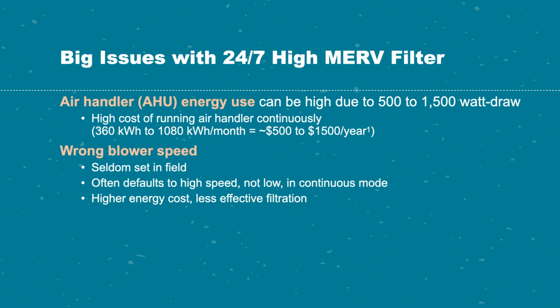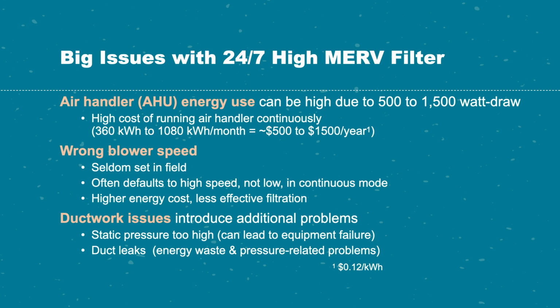So Monica, I don't know what you've seen in the work you've done, but this is a really key issue. We actually did run into 1 or 2 that were set right. It was really neat to see that, but that's not the norm. And normally the static pressure is too high. Most people don't have a clue what static pressure is. It's like, what the heck, static pressure, total external static pressure, TESP.